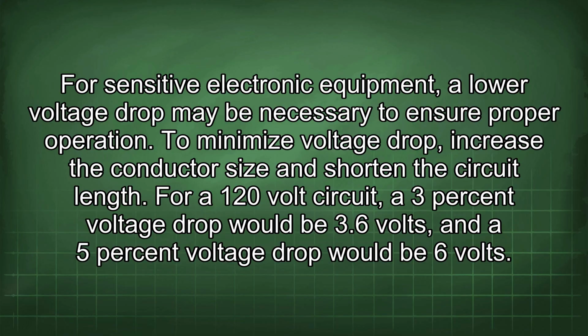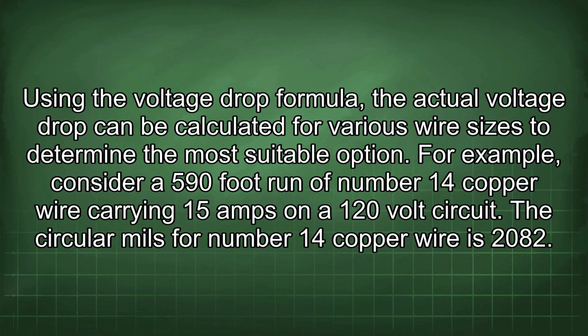For a 120 volt circuit, a 3% voltage drop would be 3.6 volts, and a 5% voltage drop would be 6 volts. Using the voltage drop formula, the actual voltage drop can be calculated for various wire sizes to determine the most suitable option. For example, consider a 590-foot run of number 14 copper wire carrying 15 amps on a 120-volt circuit. The circular mils for number 14 copper wire is 2082.